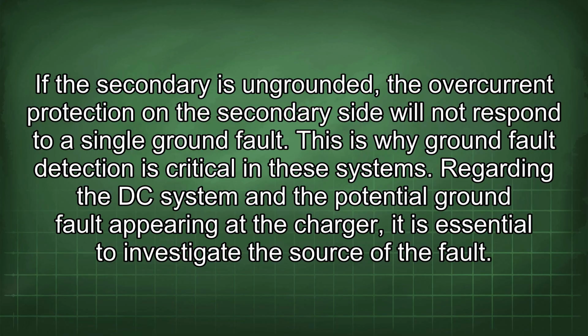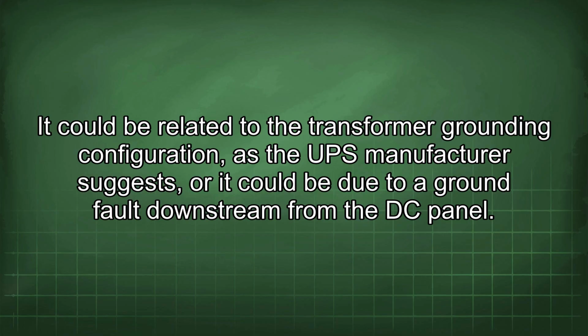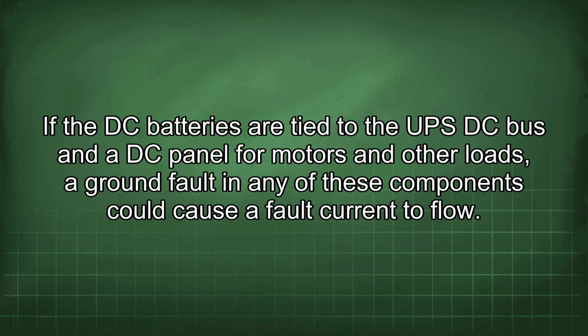Regarding the DC system and the potential ground fault appearing at the charger, it is essential to investigate the source of the fault. It could be related to the transformer grounding configuration, as the UPS manufacturer suggests, or it could be due to a ground fault downstream from the DC panel. If the DC batteries are tied to the UPS DC bus and the DC panel for motors and other loads, a ground fault in any of these components could cause a fault current flow.